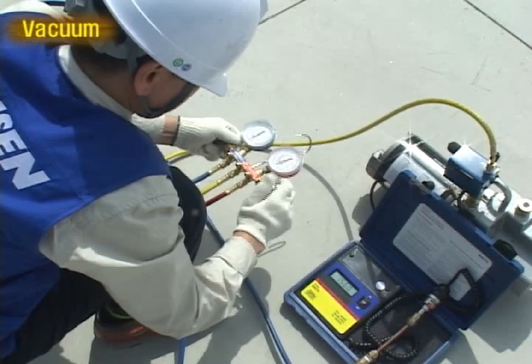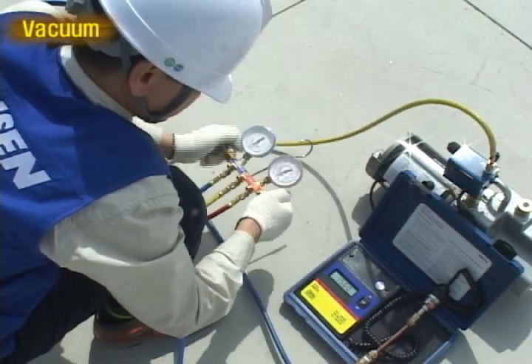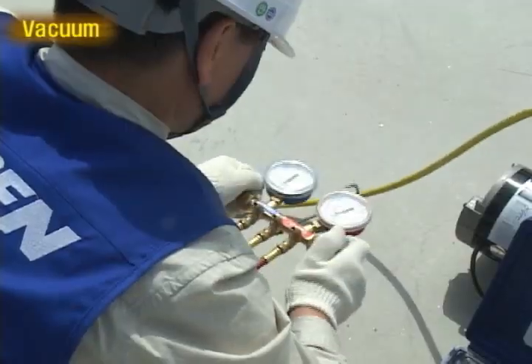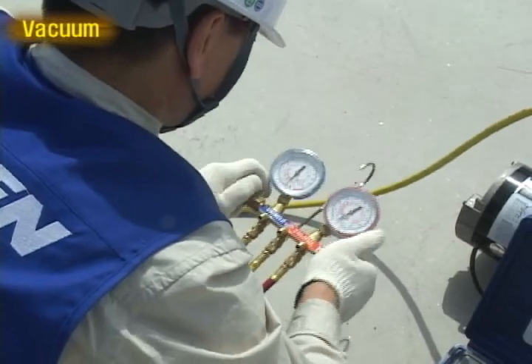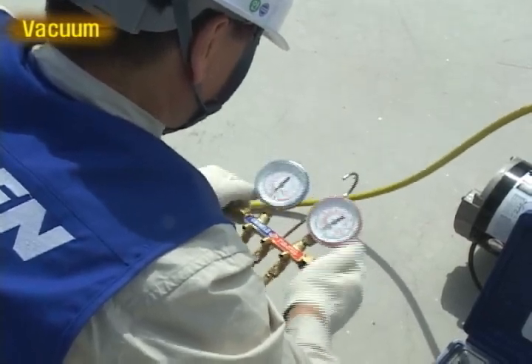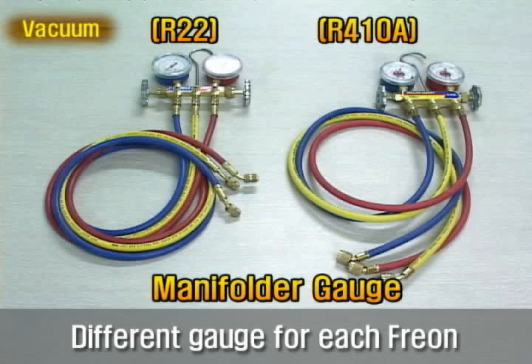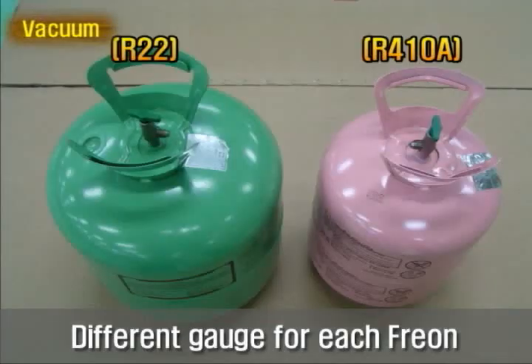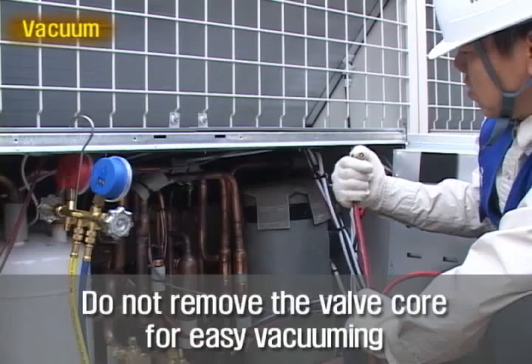Vacuuming work must be done to remove the air and moisture from inside the pipe, otherwise the unit performance can be decreased. In case the same manifold gauge is used for R22 and R410A, then there is a danger of product malfunction, so make sure that separate manifold gauges are used for R22 and R410A.